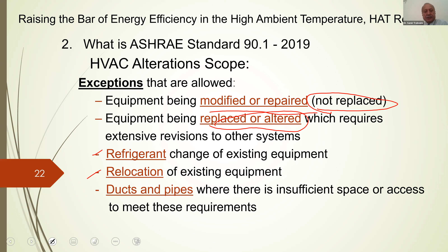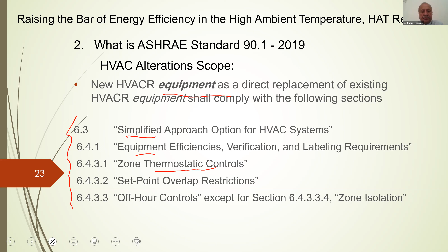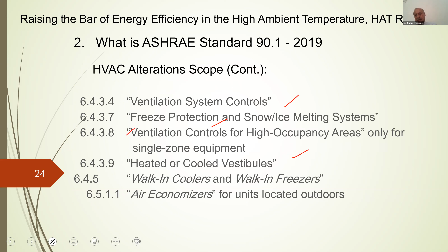Now, for equipment, if you have a direct replacement, there are technical issues to look at. First, we'll talk about it in simplified form, then go into more detail: equipment efficiencies, controls, overlap restrictions for control set points, ventilation systems, freeze protection -- not relevant here, but in colder places -- ventilation controls, heated or cooling vestibules, walk-in coolers, air economizers. The idea isn't to explain all of 90.1, but to highlight what it actually covers.